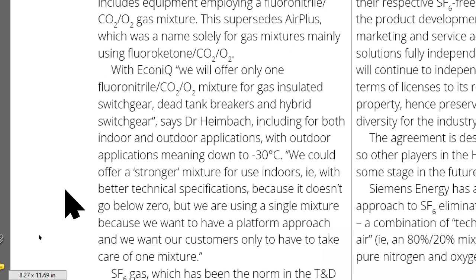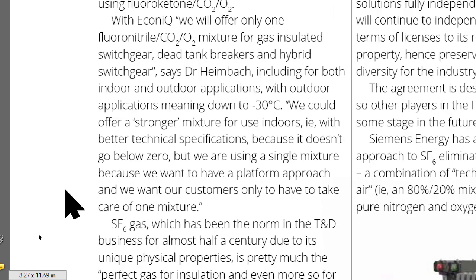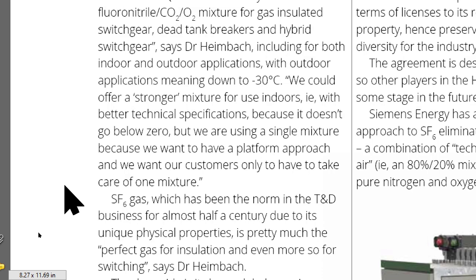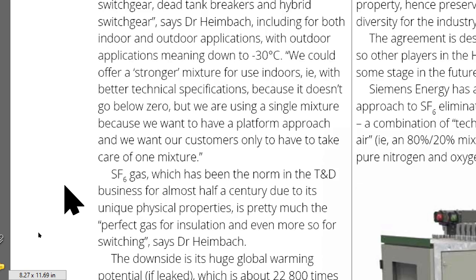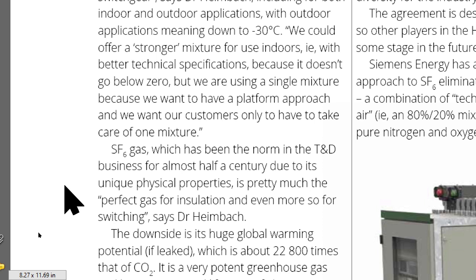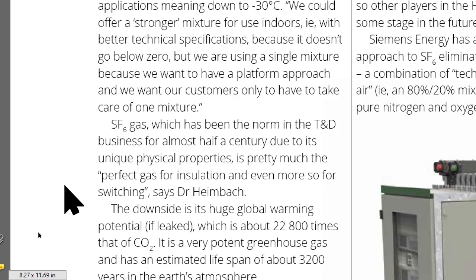With EconiQ, we will offer only one fluoronitrile CO2-O2 mixture for gas-insulated switchgear, dead tank breakers, and hybrid switchgear, says Dr. Heimbach, including for both indoor and outdoor applications, with outdoor applications meaning down to minus 30 centigrade. We could offer a stronger mixture for use indoors, for example, with better technical specifications, because it doesn't go below zero. But we're using a single mixture because we want to have a platform approach, and we want our customers only to have to take care of one mixture.